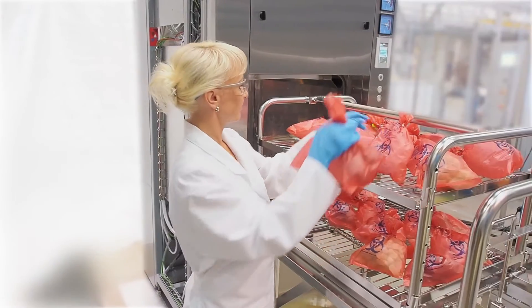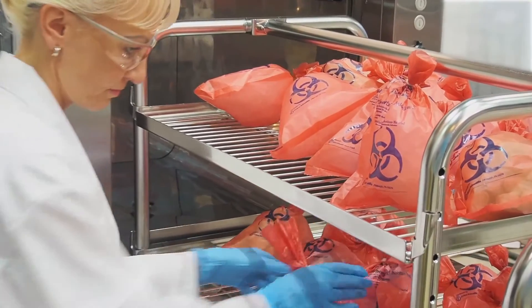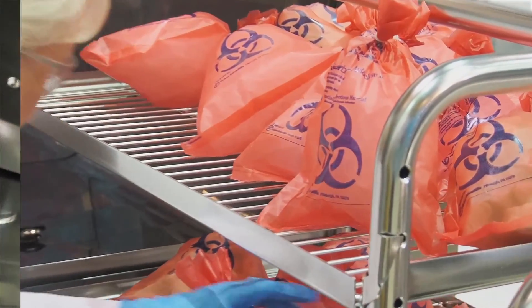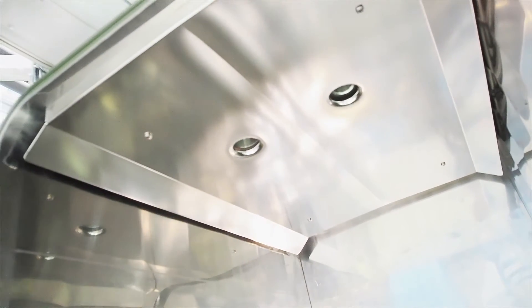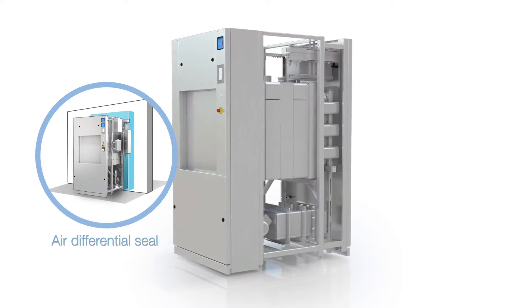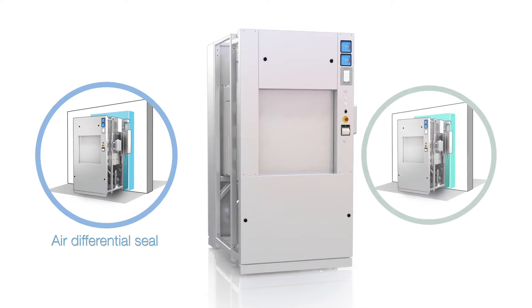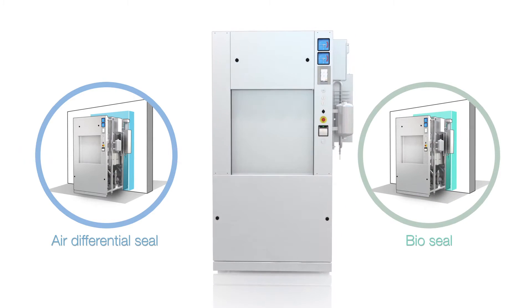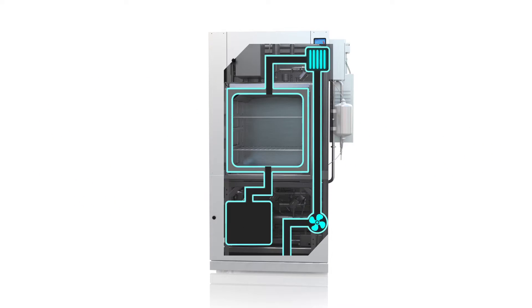The pathogenic nature of waste material from biosafety laboratories requires special decontamination processes. For this reason, the double door 77 Series sterilizer can be configured to decontaminate waste material in biocontainment facilities and fitted with an air differential seal to minimize air flow between non-sterile and sterile areas. For more critical applications, a bio seal can be provided to form a hermetic barrier between hot and cold zones, ensuring no waste or contaminated air is released into the environment.